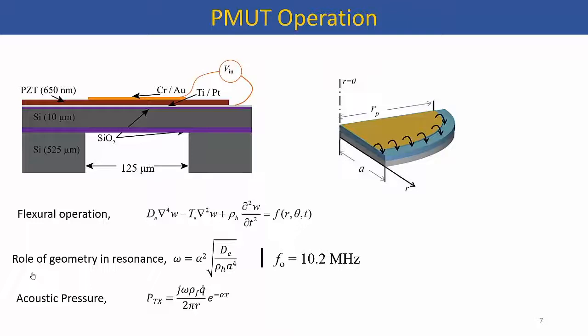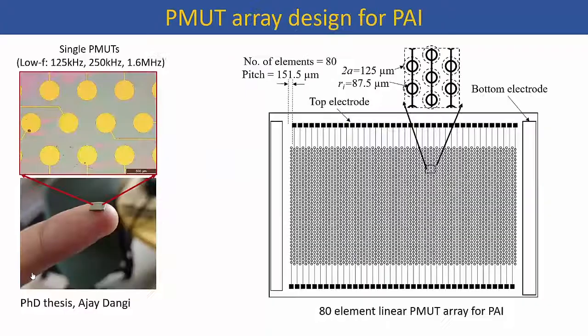We fabricated PMUTs with 125 micron diameter, 10 micron silicon as the passive layer, and around 650 nanometer thick PZT as the active layer. The expected in-air resonance is around 10 megahertz, but underwater there is some frequency shift. The array design has 80 elements; each element is a linear combination of multiple PMUT cells. Individual PMUT cells are 125 microns and placed in staggered arrangements to achieve as high a fill factor as possible, giving around 150 micron pitch from one element to the next.